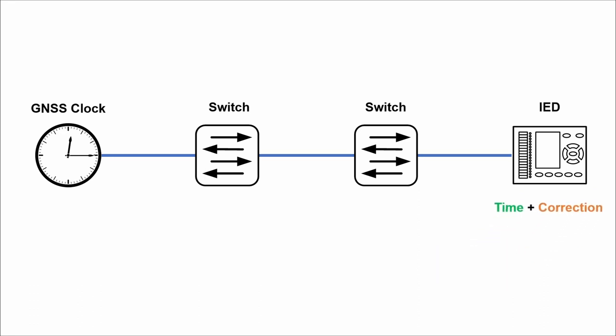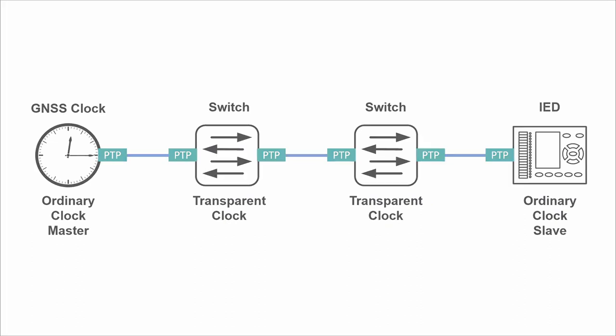Ethernet switches in this scenario have a role of so-called transparent clock and therefore need to support PTP protocol with hardware-based time stamping using specialized hardware components for each ethernet port.